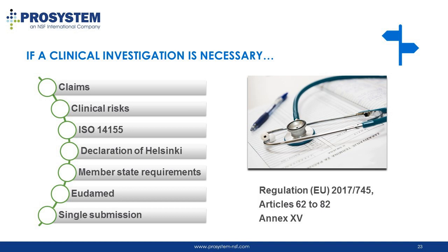If sufficient data for the device under evaluation is not available and equivalence cannot be claimed, a clinical investigation will be necessary. To perform a clinical investigation, keep in mind that claims and clinical risks of the device should be taken into account when preparing the study protocol. In addition, not only the regulation, but also standard ISO 14155, the Declaration of Helsinki, and specific requirements of the member states of the EU have to be followed.